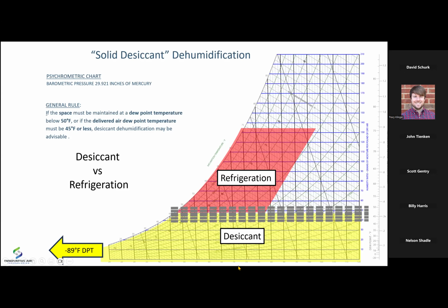But if you're up here and you're at 70 or 75 degrees Fahrenheit and 50 or 55 or 60% relative humidity, traditional refrigeration systems, cold coil systems play well. Let the plumbers plumb. I got no problem with that. Tracy and gang have all kinds of solutions that are very cost effective, very efficient up here in the red area. But sometimes these systems overstep their bounds a little bit. They try to do a little bit more than they should or could. There may be reasons. Maybe it wasn't designed quite right. Maybe the equipment's getting older. Maybe the space has been repurposed and it requires lower relative humidities. And you don't want to throw the baby out with the bathwater. You'd like to use this system if you can. Maybe it's brand new, just can't hit the mark.